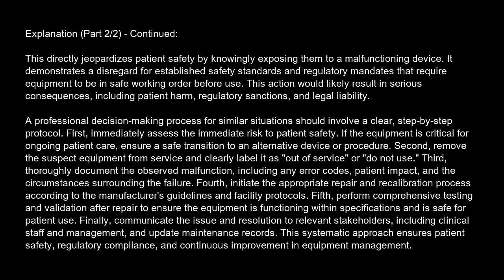A professional decision-making process for similar situations should involve a clear, step-by-step protocol. First, immediately assess the immediate risk to patient safety. If the equipment is critical for ongoing patient care, ensure a safe transition to an alternative device or procedure. Second, remove the suspect equipment from service and clearly label it as out of service or do not use. Third, thoroughly document the observed malfunction, including any error codes, patient impact, and the circumstances surrounding the failure.